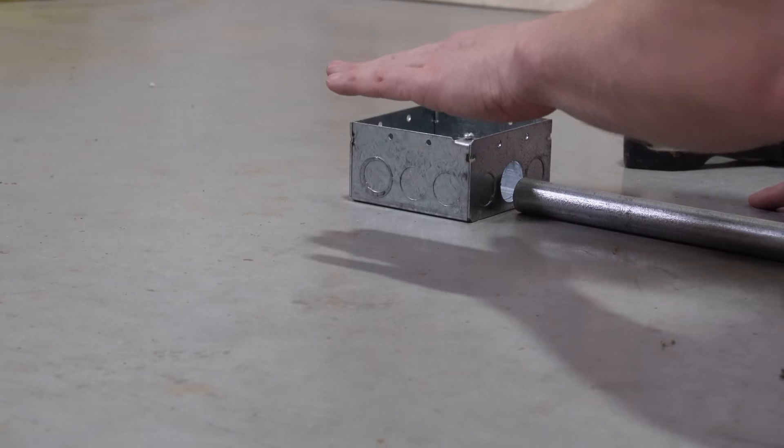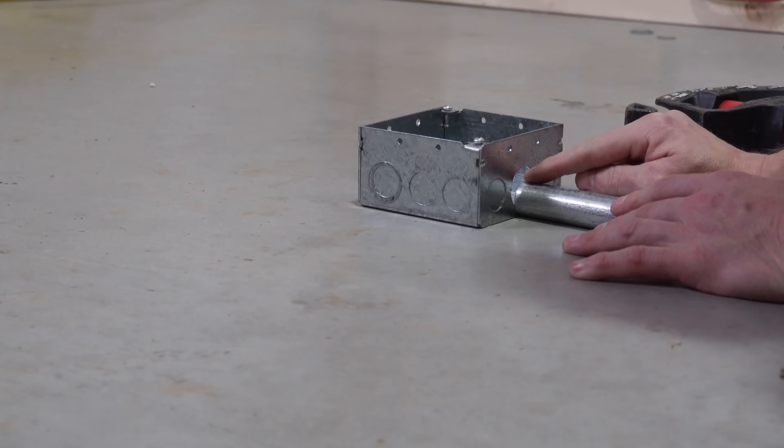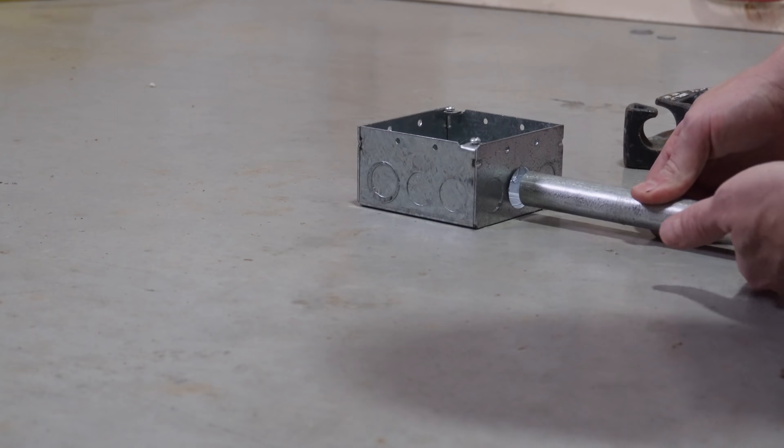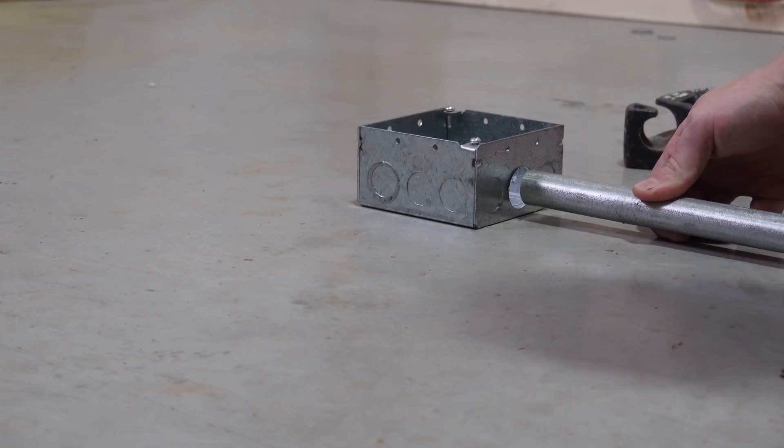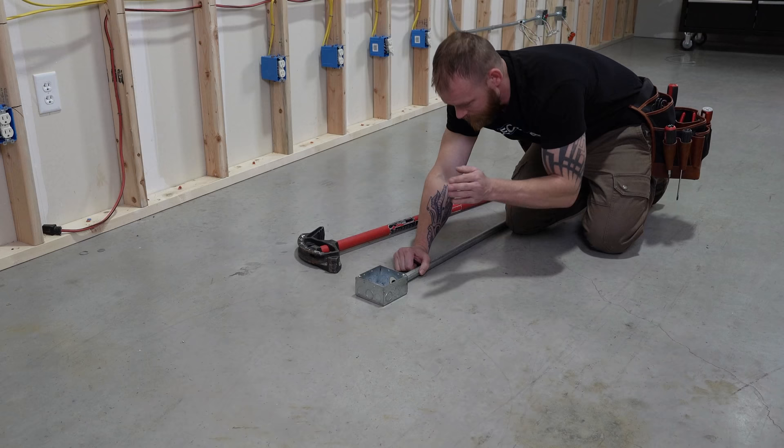If you look right here we've got this box and this piece of conduit would not actually go into that hole. We would need to raise it a little bit, but we're not just going to raise it like that because then we won't be able to attach a strap since there's a gap back here. If there's a piece of wood or something running behind here we can't strap that down. So we still need the rest of the conduit to be down, but we need to bend this conduit up so that we can get a connector on that thing and get it in the right spot.